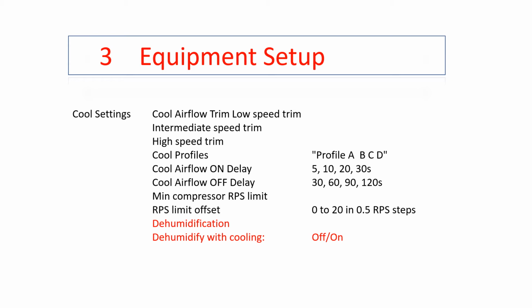Under cool settings, we'll have our airflow trim for low speed, intermediate speed, and high speed. So when you go to the fan and turn it on, all 3 settings can be trimmed on this screen. We still have our A, B, C, D profiles for dehumidification or for ramping of the blower. Keep in mind your inverter is not going to cycle 3 to 6 times an hour. So this ramping will occur, but it may only occur once or twice an hour.